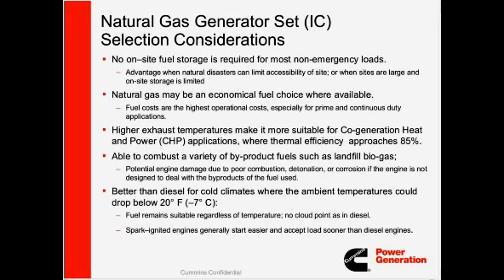Even though diesel generators are known for better transient performance than natural gas generators, there are situations where, in cold climates, a natural gas generator or a spark-ignited engine may start easier and accept load sooner than a diesel engine. And it's also recommended for many cold climates where your temperature drops below 20 degrees Fahrenheit, because the fuel remains suitable regardless of the temperature, and there is no cloud point as you have in diesel fuel.